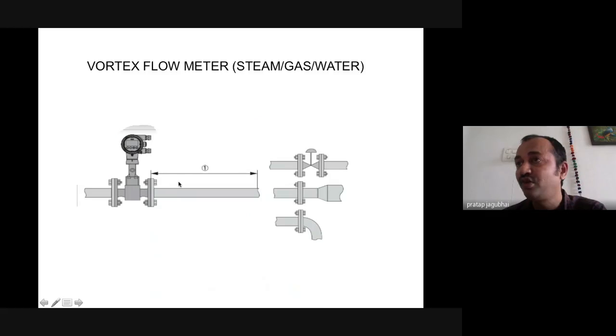Another important flow measurement is the vortex type flow measurement, which is basically a frequency type measurement, where you have a vortex flow piezo sensor inserted inside the media where we need to measure the flow. It measures the vortices. The frequency change is sensed by this pickup piezo sensor and is converted into mass flow as well as volumetric flow. So this is very widely used for steam, gas, and water applications, very reliably and accurately.